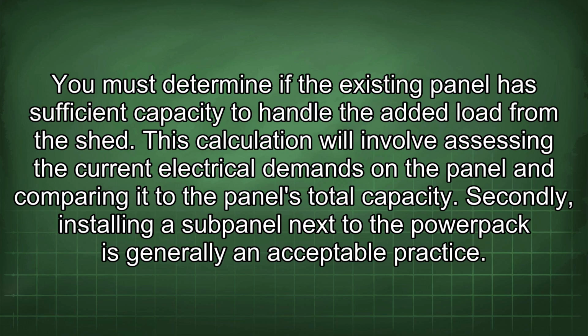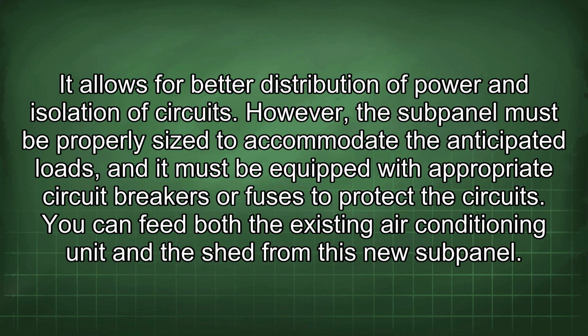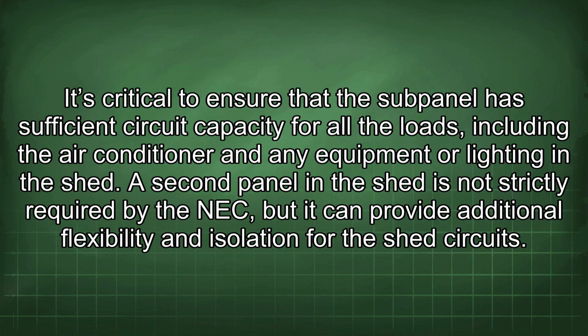Secondly, installing a subpanel next to the power pack is generally an acceptable practice. It allows for better distribution of power and isolation of circuits. However, the subpanel must be properly sized to accommodate the anticipated loads, and it must be equipped with appropriate circuit breakers or fuses to protect the circuits. You can feed both the existing air conditioning unit and the shed from this new subpanel. It's critical to ensure that the subpanel has sufficient circuit capacity for all the loads, including the air conditioner and any equipment or lighting in the shed.